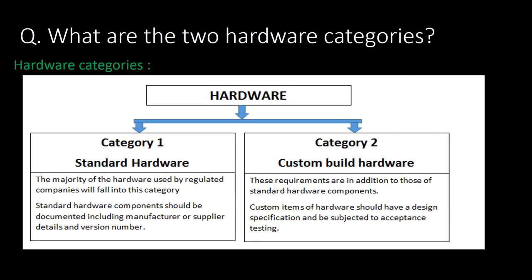What are the two hardware categories? Category 1 is standard hardware. The majority of hardware used by regulated companies falls into this category. Standard hardware components should be documented including manufacturer or supplier details and version number. Category 2 is custom-built hardware. Custom items of hardware should have a design specification and be subjected to acceptance testing.